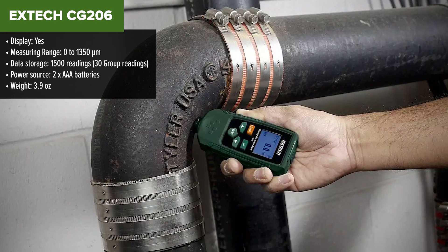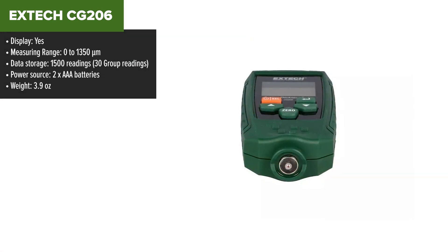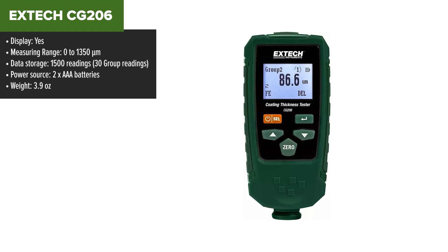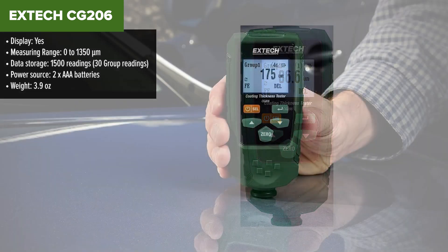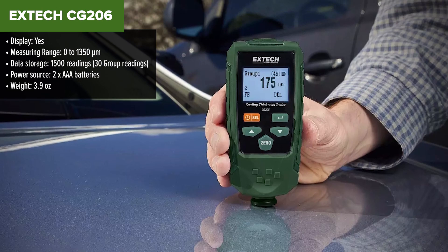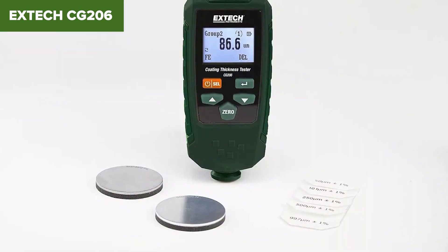The Extech CG206 is a high-precision coating thickness tester designed for both ferrous and non-ferrous substrates. It features automatic substrate recognition, utilizing magnetic induction for ferrous materials and eddy current measurement for non-ferrous materials. This device is user-friendly, with an intuitive menu system and dual working modes. It offers extensive data storage, capable of holding up to 1500 readings, and includes software for easy data transfer and analysis via USB.